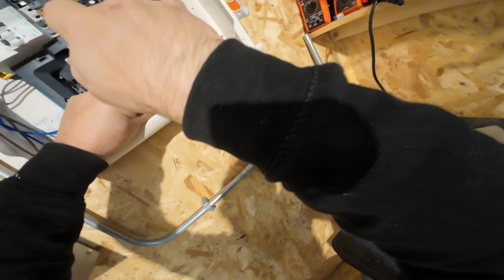So we've got some more singles going in, drawing back the other way this time. I don't know why I swapped round from one to the other, but change is as good as a rest, doesn't really make that much difference. These are now returning back to that metering kit on the underside of the Schneider board. It may not be that easy to see on the video, but there are separate terminals for this. So the meter basically has your inputs coming into it, and then they loop across over to the main switch out of the meter. That's just a way to measure what an individual board's been doing.